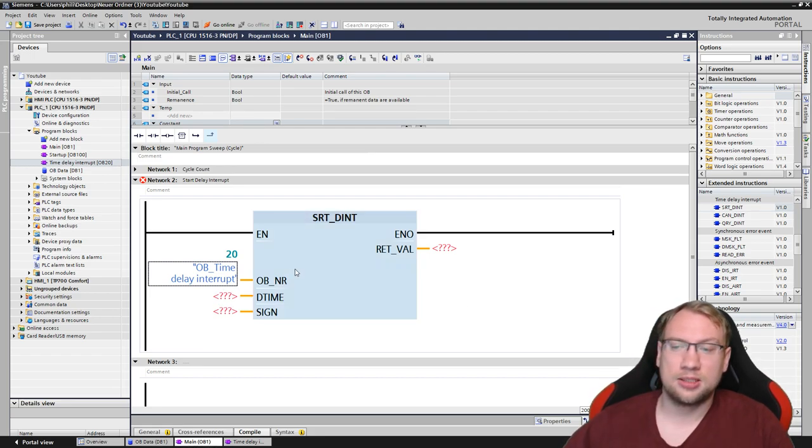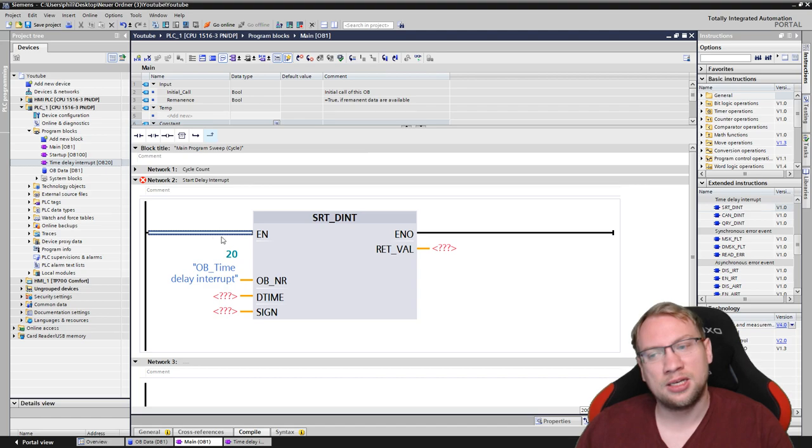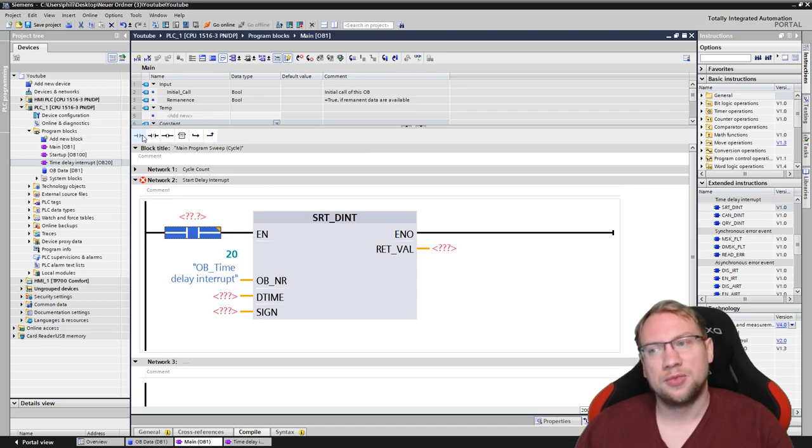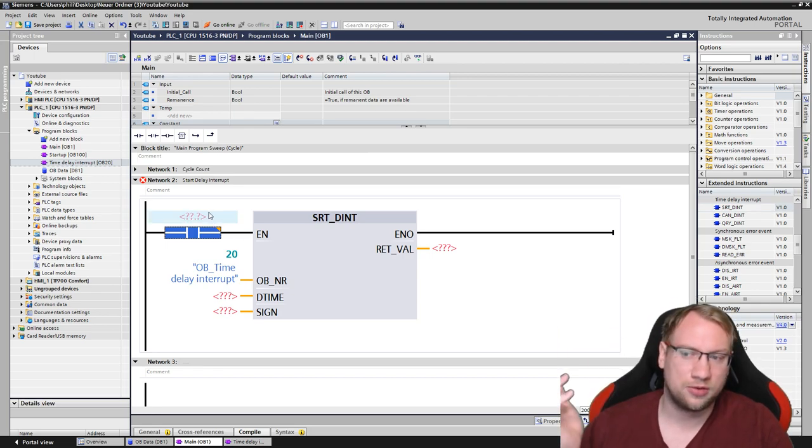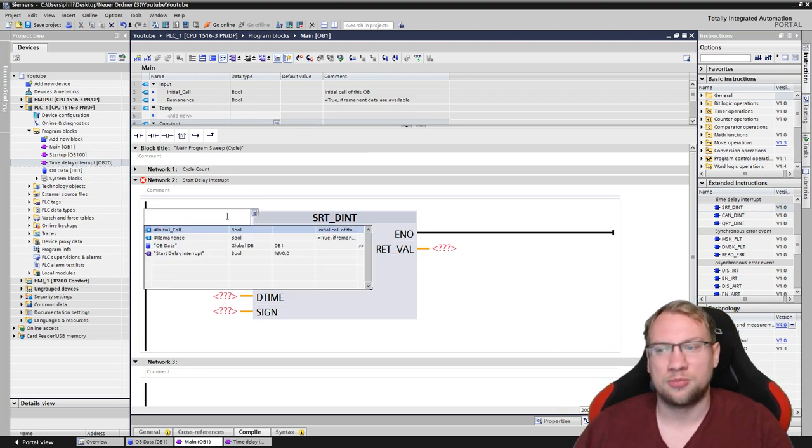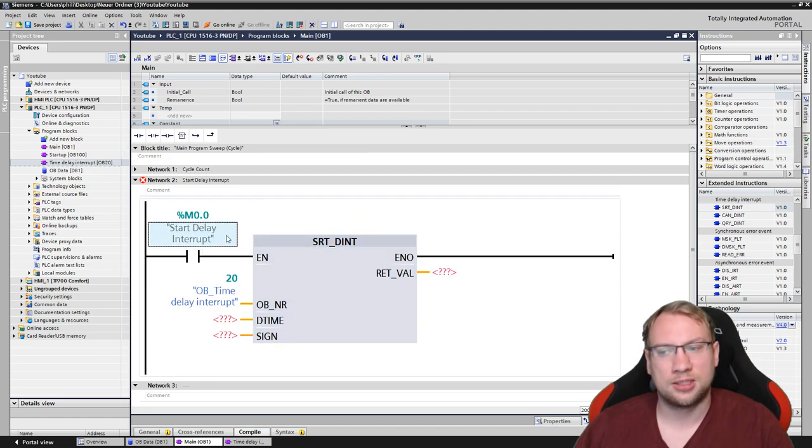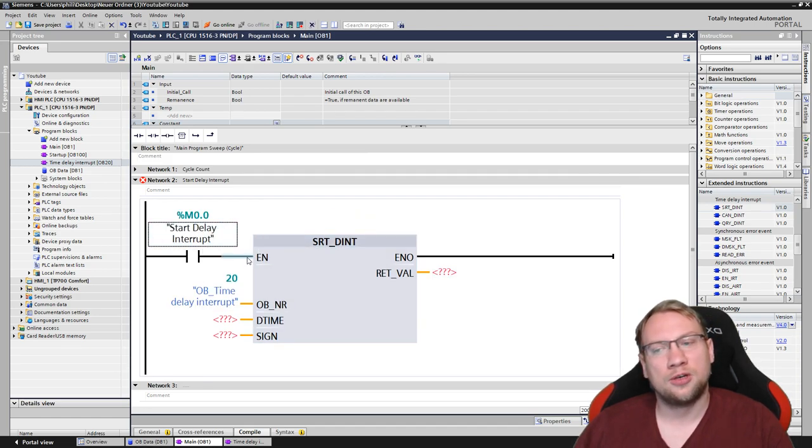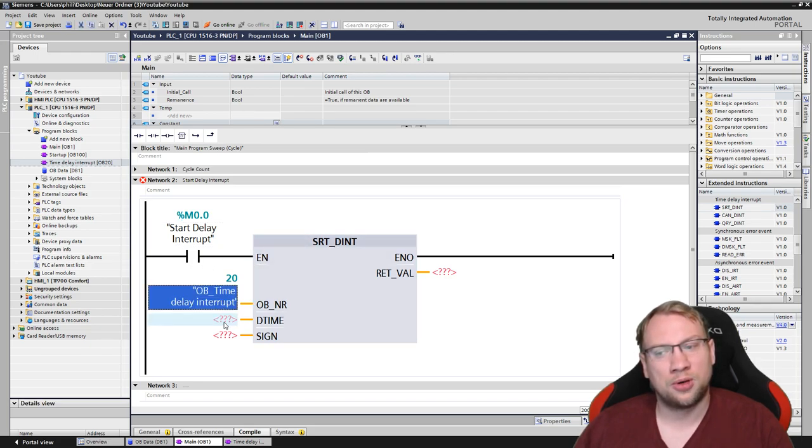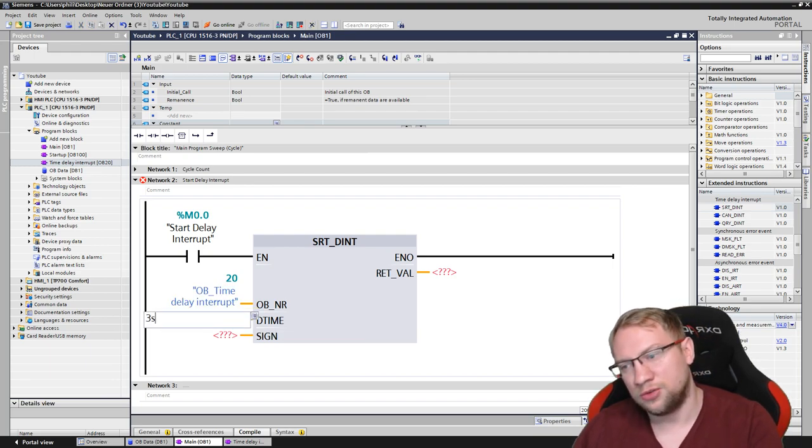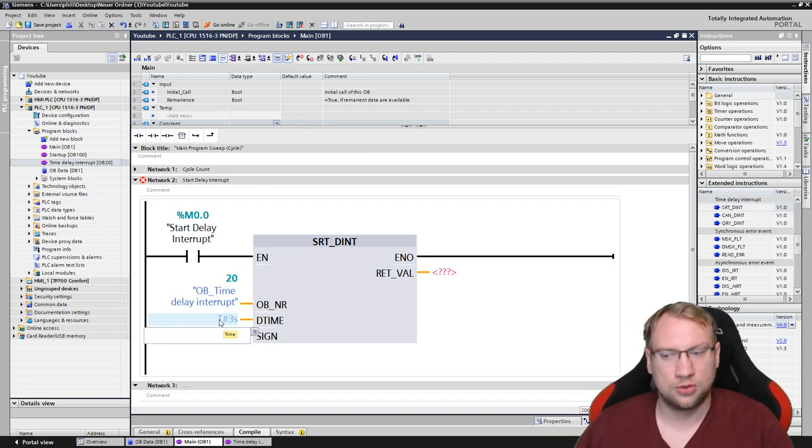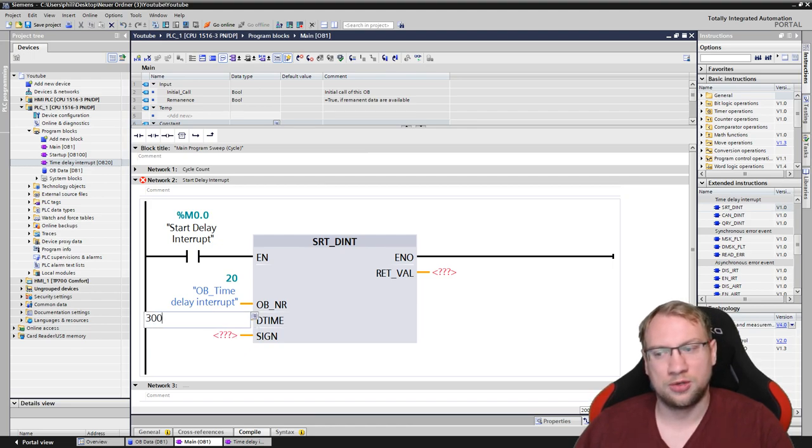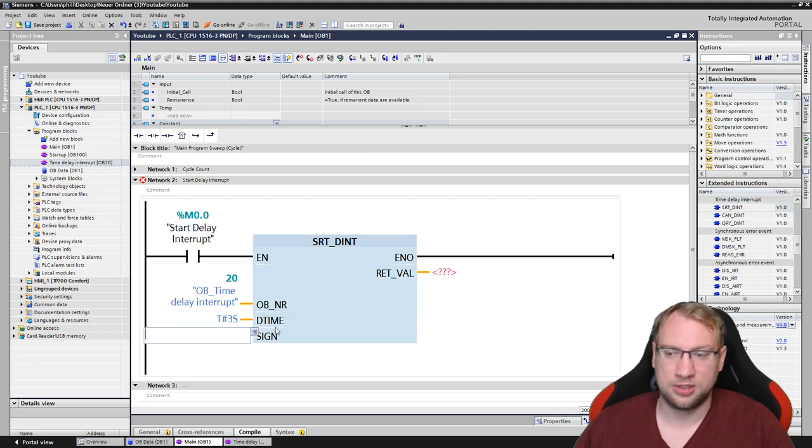The second is, this gets executed whenever we have an enable here. So, I will just put any signal. You could put any other signal, of course. I will just put a signal that I have prepared, which is just a memory saying start delay interrupt. Once we see a rising edge here on the enable input, this one will be called after this time, which I will say 3 seconds. You could also put a variable, or if you put 3,000, that's actually 3,000 milliseconds, meaning 3 seconds.